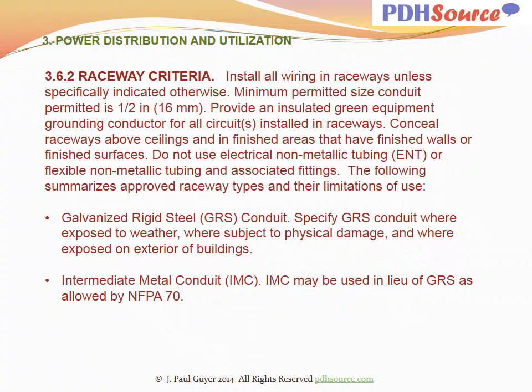The following summarizes approved raceway types and their limitations of use. Galvanized rigid steel conduit: specify GRS conduit where exposed to weather, where subject to physical damage, and where exposed on exterior of buildings. Intermediate metal conduit, IMC, may be used in lieu of GRS as allowed by NFPA 70.